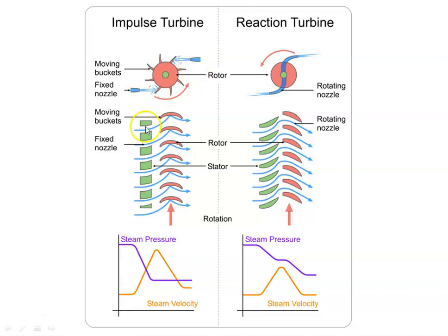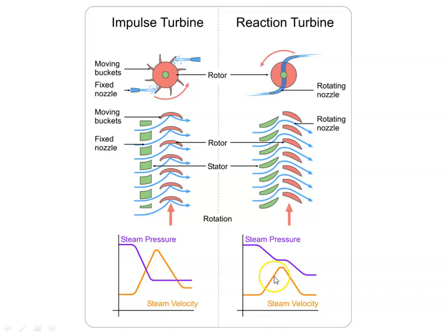Here we have a nozzle — the green color is the nozzle. It is a fixed nozzle attached to the casing of the machine, and you have the moving blade. The purpose of the moving blade is to convert the velocity of the steam into work done. The steam pressure decreases across the nozzle and the pressure remains constant in the moving blade. The velocity is increasing in the nozzle — the drop in pressure is converted into increasing velocity, and that velocity is utilized in the moving blade to produce power.